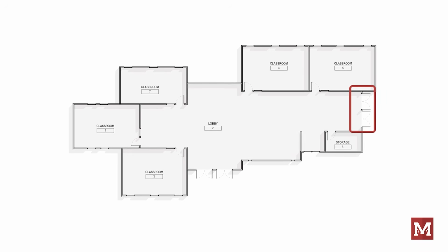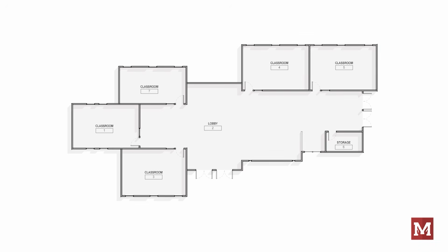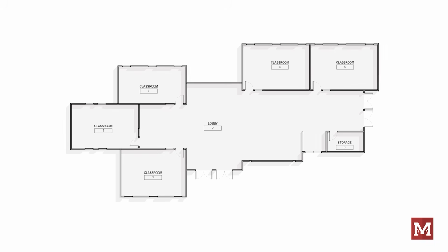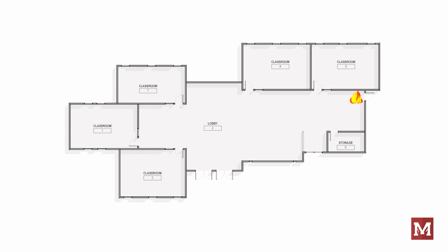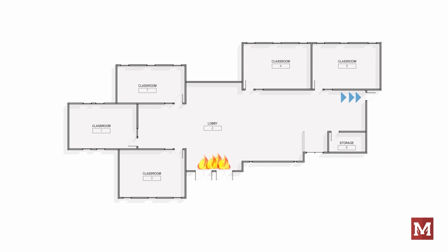The concept is that if one exit is unavailable, we need the other exit to accommodate the occupants. Now, don't go thinking we need to size that second exit for the entire occupant load. We don't. We distribute occupant loads equally amongst exits. But back to the question, why not have one very large exit? Let's say in this scenario, I lose my really small exit. No problem. We have that huge exit. That can take a whole lot of people. Yeah, but what if I lose the big exit? Well, now the remaining smaller exit is undersized for the occupant load. It can't handle the volume of people.